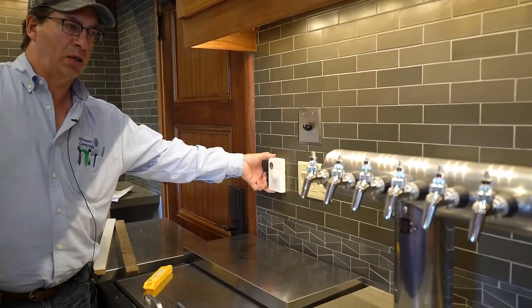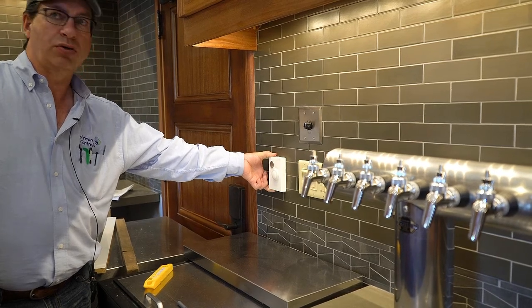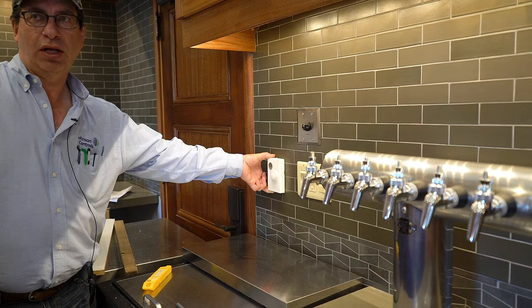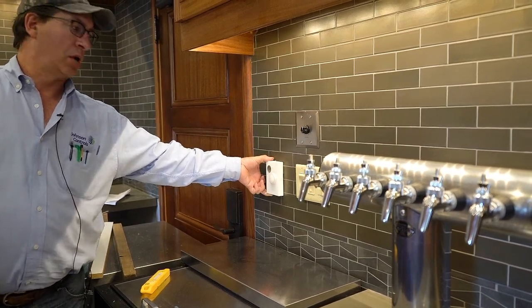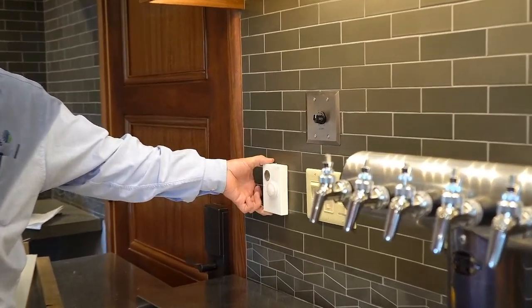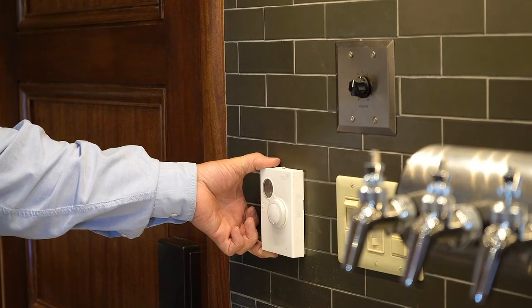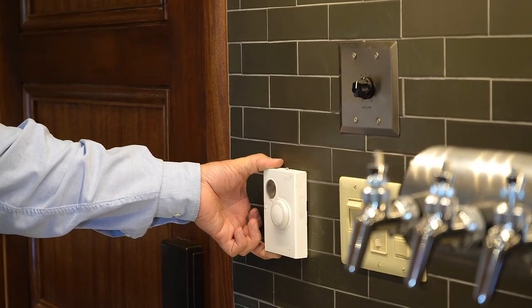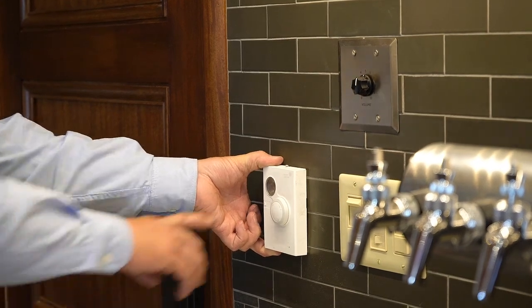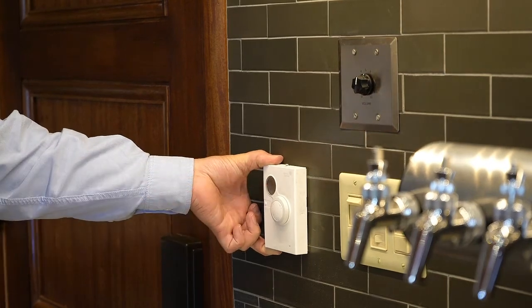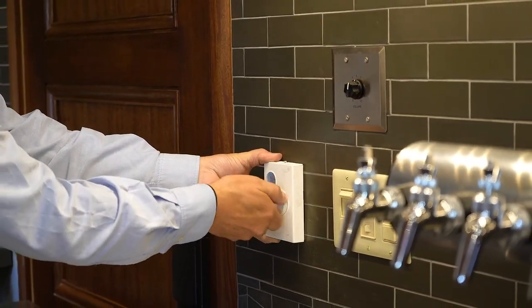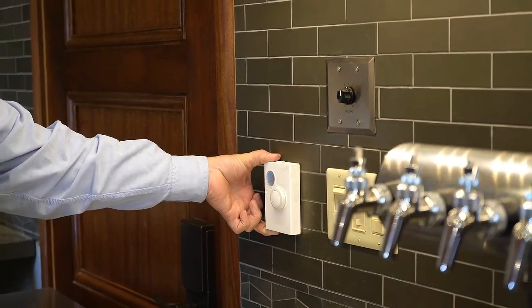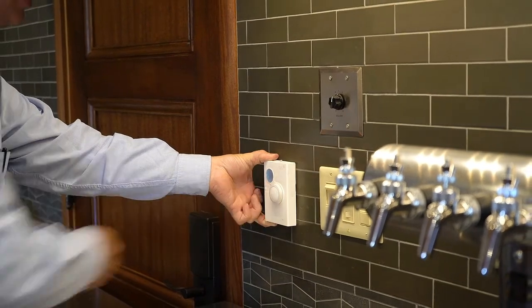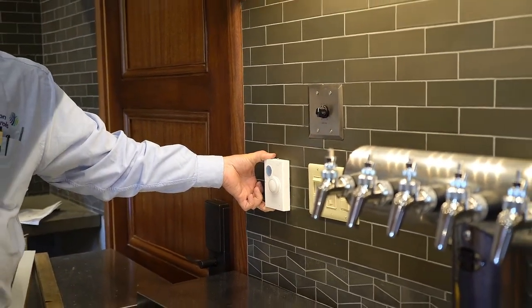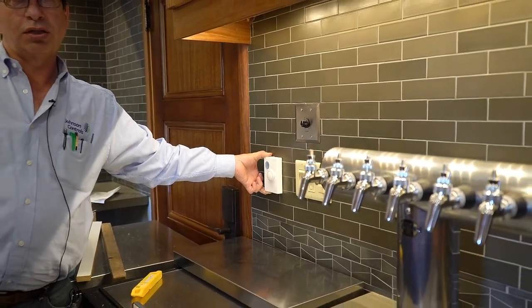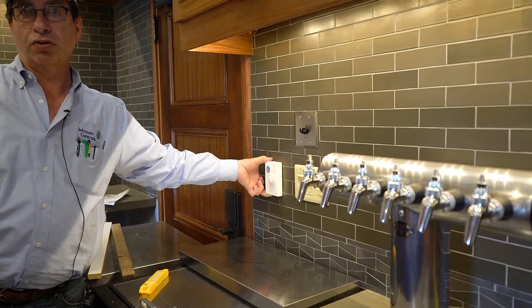So we're in the map room, and we're back here by the beverage dispenser. This thermostat here controls fan coil 8. Fan coil 8 is the one that does heating only in the map area. These are Johnson Controls stats. Those other stats we looked at were Daikin stats. We didn't supply those other stats, they came with the units. This is a standard Johnson Controls stat. If you look on the display, this will display the actual room temperature. If you turn the dial, it'll start flashing, and that'll be your actual room set point. So you can turn this dial to set your set point, and then that's what it'll try to control to. So these are a standard JCI thermostat. This is what will be tied back to our FEC controllers.